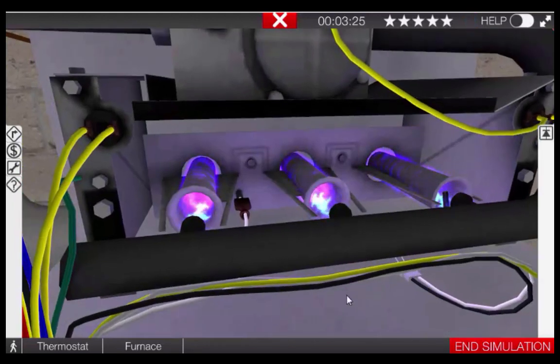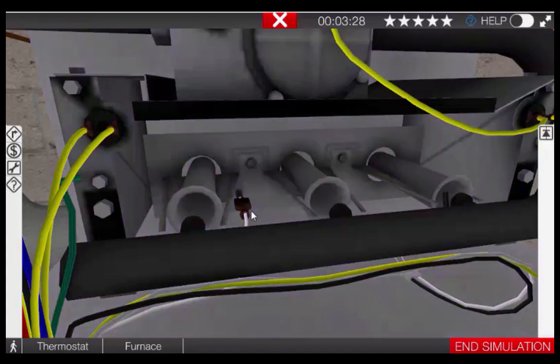As you can see, this is not happening here. This may be the result of a faulty IFC, which is receiving an adequate signal but not recognizing it, or it could be simply something as an open ground wire or an open sensor wire. Let's check it out.